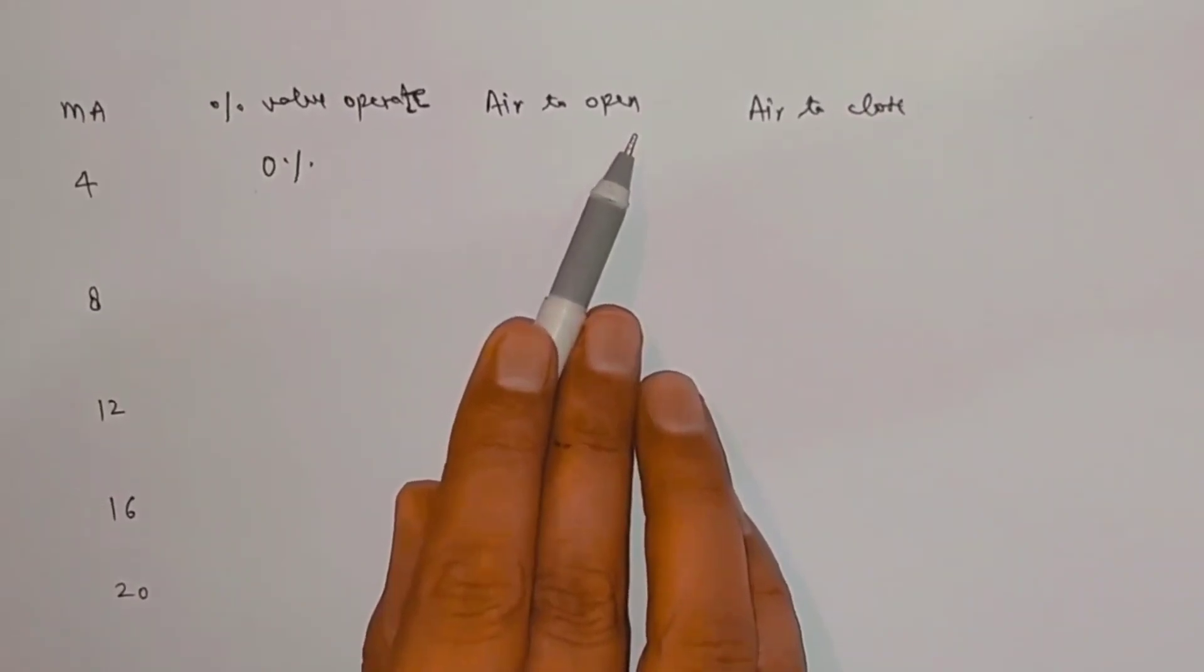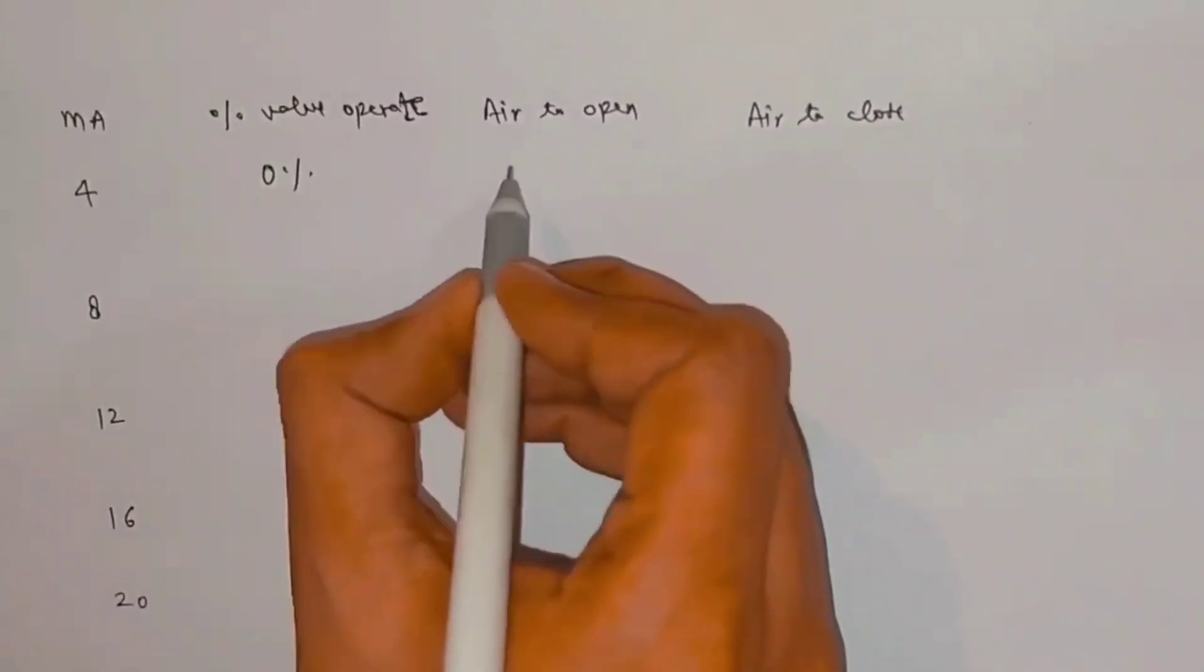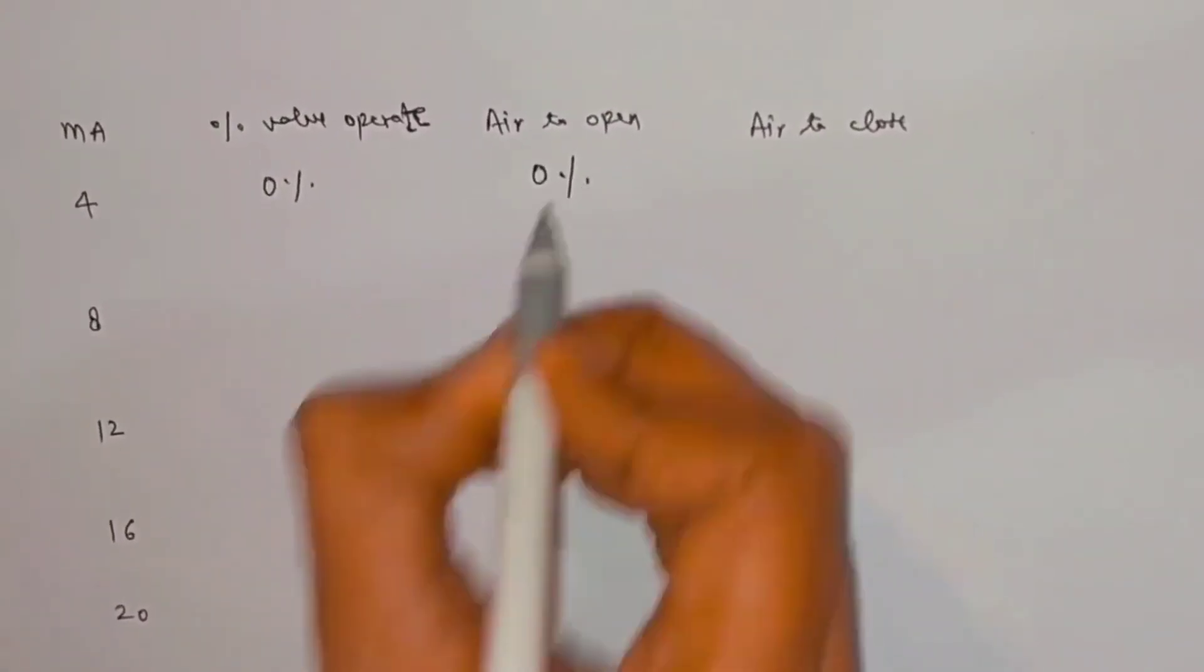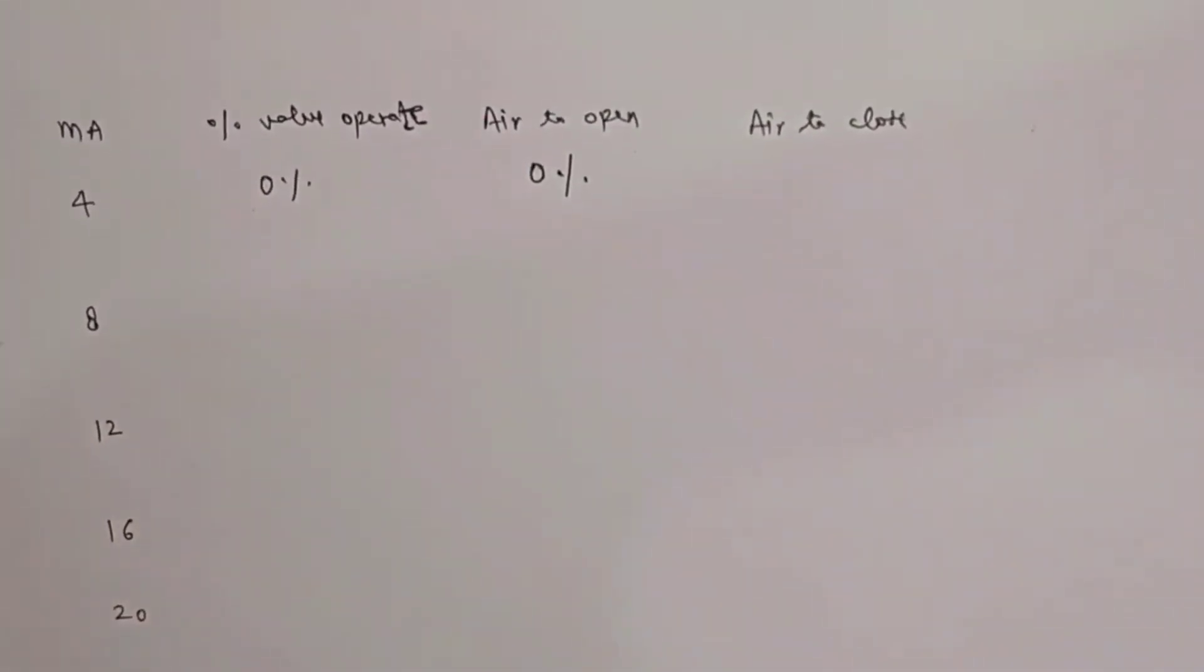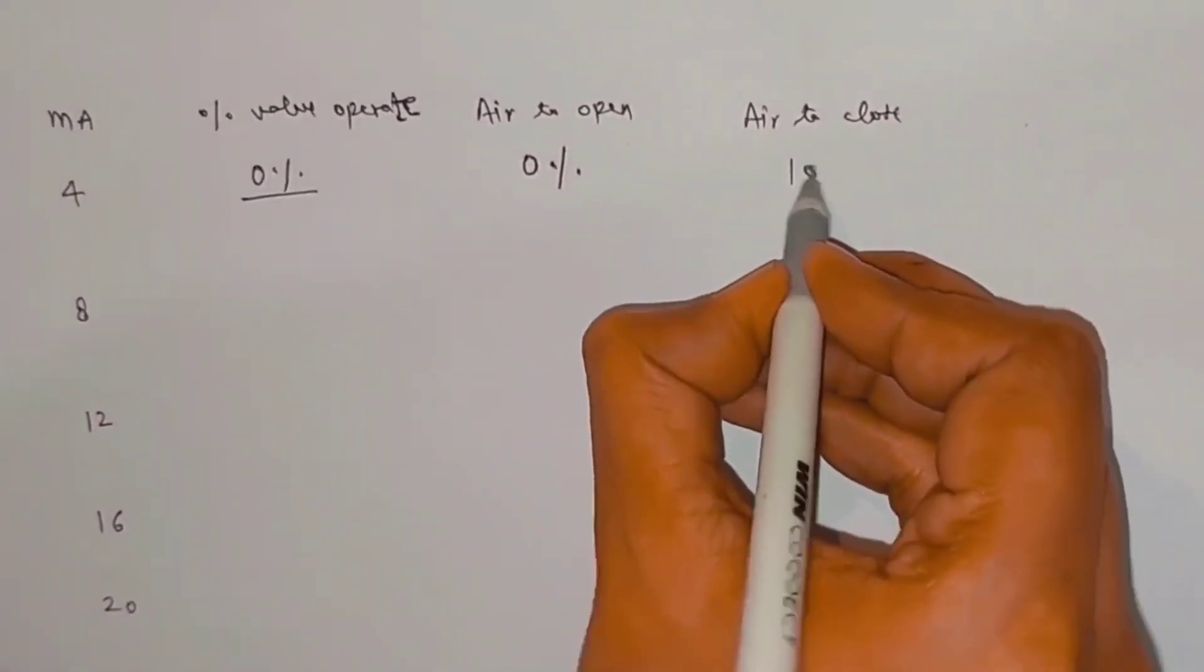When we take air to open control valve and when it will operate 0%, its percentage opening will be 0%. But when we take air to close control valve and it will operate 0%, then its opening percentage will be 100%.